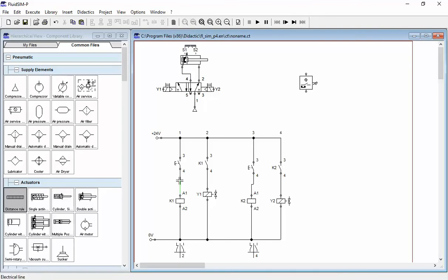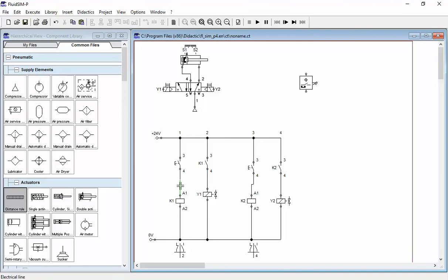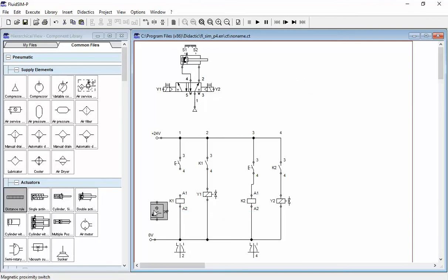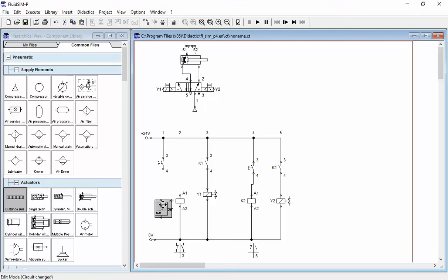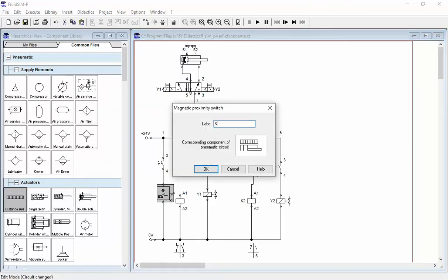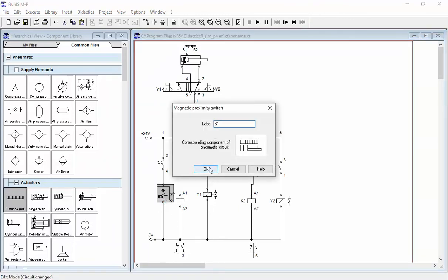We have a push button to operate relay K1. Now, what I will do is remove the line from here and cut the line by this way. I will take the sensor here. I will use push button to give signal or to connect power to sensor S1. I will write here: this one, S1, it means reed switch. S1 has to be mounted on the cylinder body.